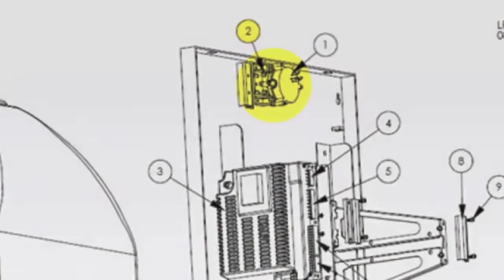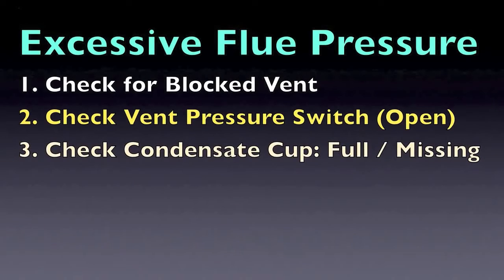The blocking code FLU is tied in series with the condensate float, flue pressure switch, and condensate cup engagement switch only on the MC boilers.